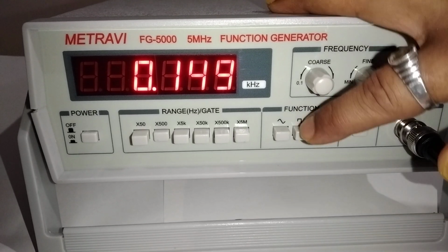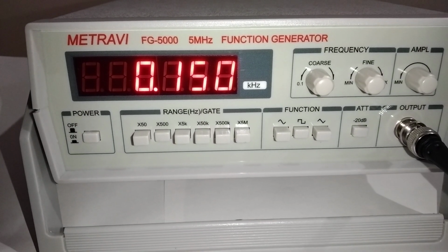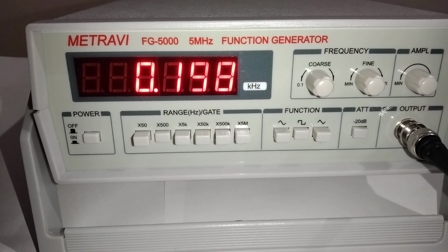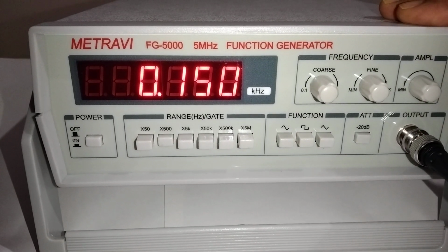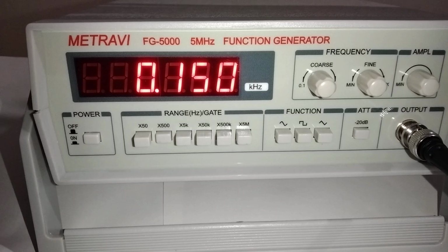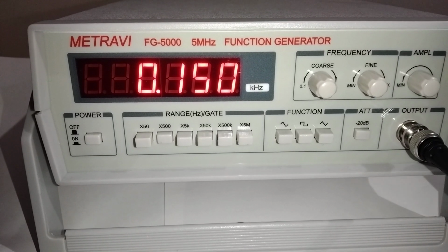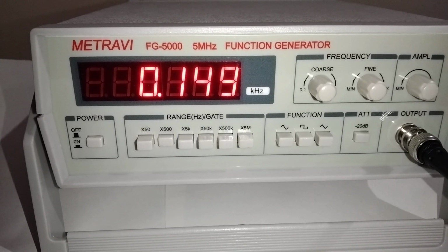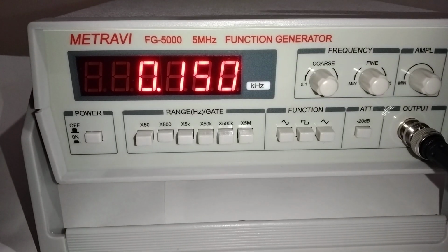Now when you press this switch, that is for a square wave, then there is a rise time from 0 to maximum in a square. So it is less than 40 nanosecond. As low as desirable, so quick change is desirable, so it is less than 40 nanosecond, and the total power consumption of the instrument is 20 watt. So this is the functionality from the front end of the instrument.